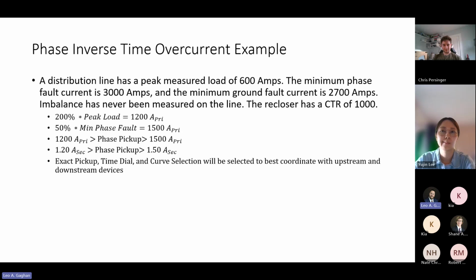So we're going to pick a range of acceptable pickups. We'll talk about the rest. If you look at 200% of the peak load, that's 600 amps, that comes out to 1,200. We need to be above that 1,200 amps. If you look at 50% of that minimum phase fault current, at 3,000 cut in half, that gets you to 1,500. We've got to be set below that. So our phase pickup has to be greater than 1,200 and less than 1,500.